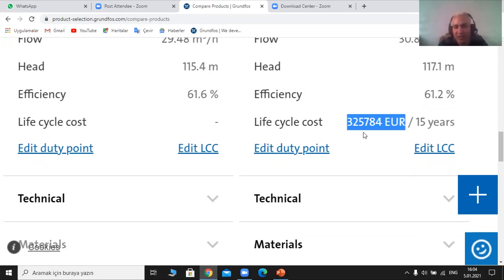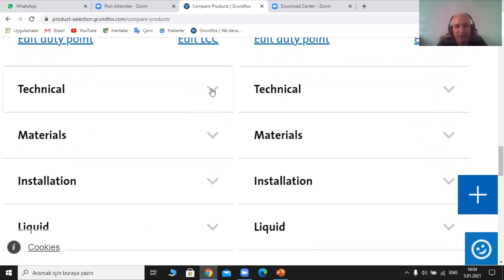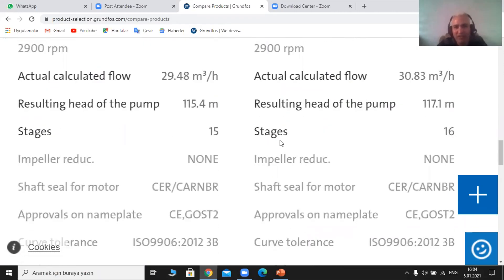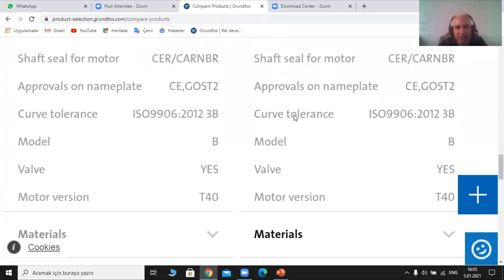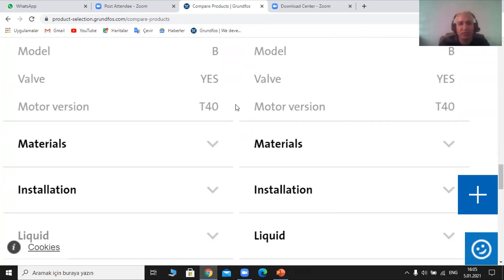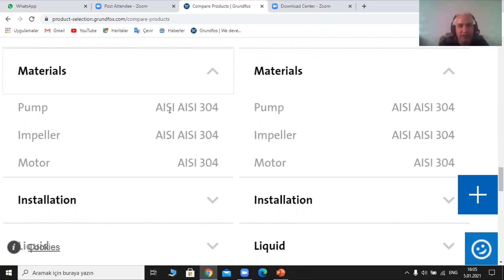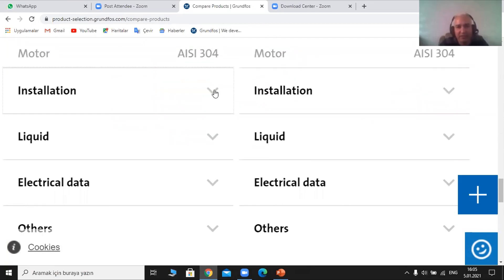Even for the life cycle cost for 15 years — as I said, there are specified parameters I changed. Then I have technical differences I can click on and see some specifications. Here are 15 stages versus 16 stages, and we have more head and more flow capacity. Number of parameters include valves, and as Yasser asked about motor version — maybe I can choose two different motors and compare among them. The material: what materials are used for the pump, the impeller, the motor.